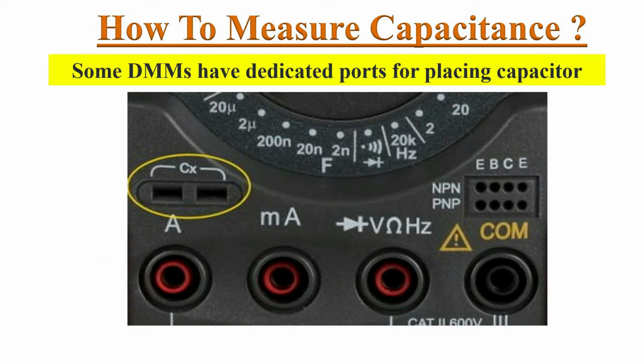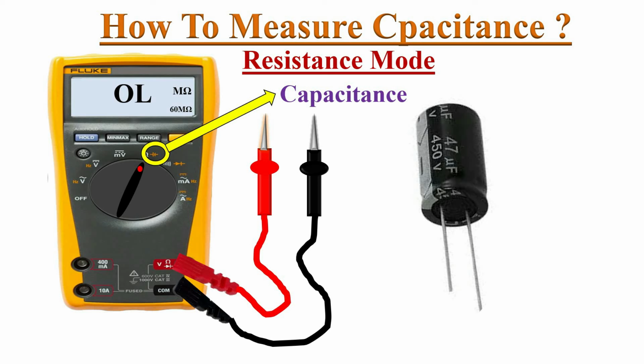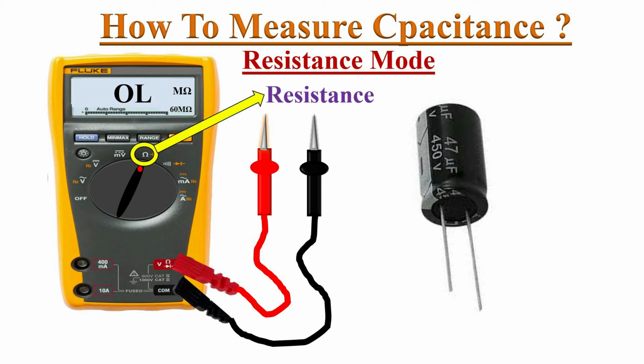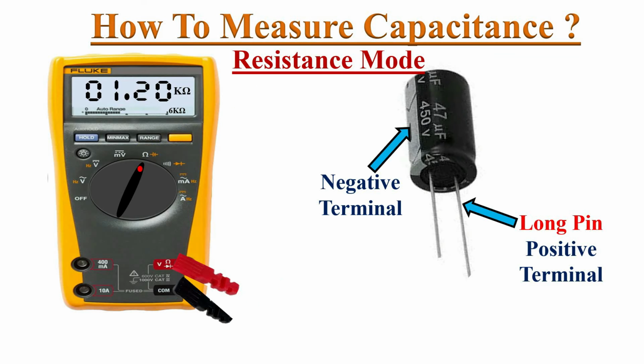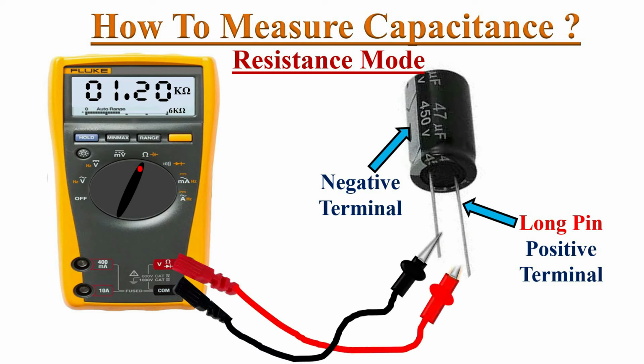Some multimeters have dedicated ports like this for placing a capacitor to measure its value. If your multimeter doesn't have a capacitance setting, you can use resistance mode to test the capacitor. This method might not be accurate and doesn't give the capacitance value, but we can differentiate between a good and bad capacitor. Set the multimeter in ohmic range. Connect the multimeter probes to the capacitor terminals, negative to negative and positive to positive.